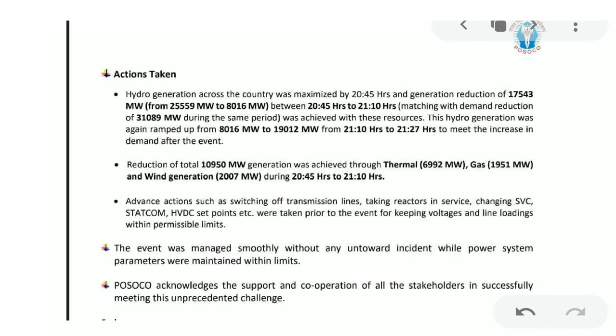You can see that the hydro generation across the country was maximized by 2045 hours, and there was a generation reduction of 17,543 megawatt between 2045 and 2110, matching with a demand reduction of 31,089 megawatt. So this demand reduction, as you can see, was achieved with these resources.